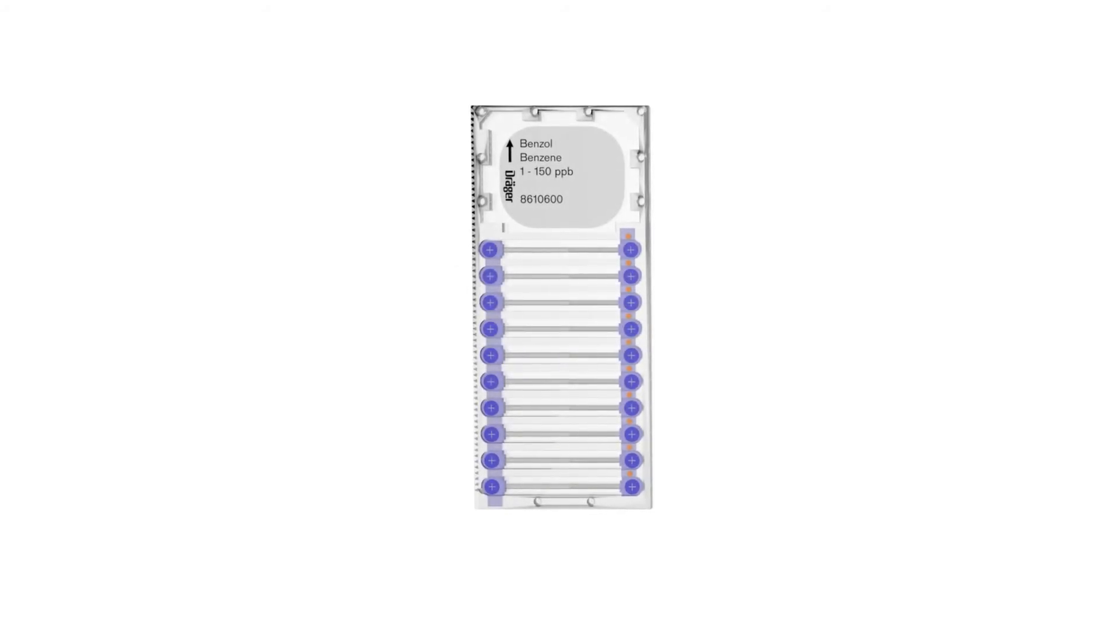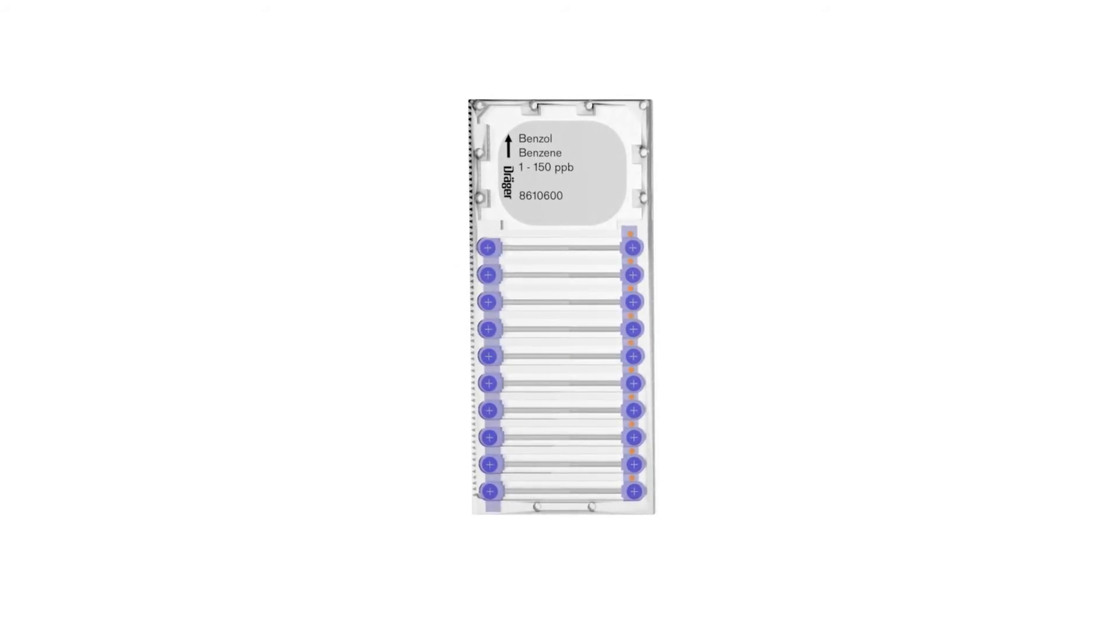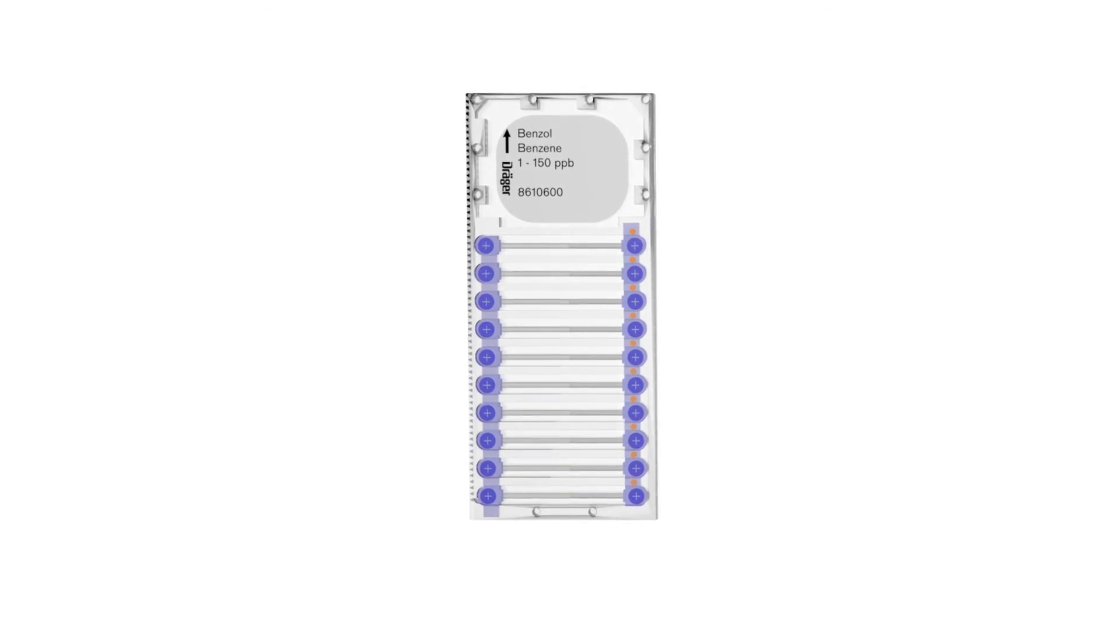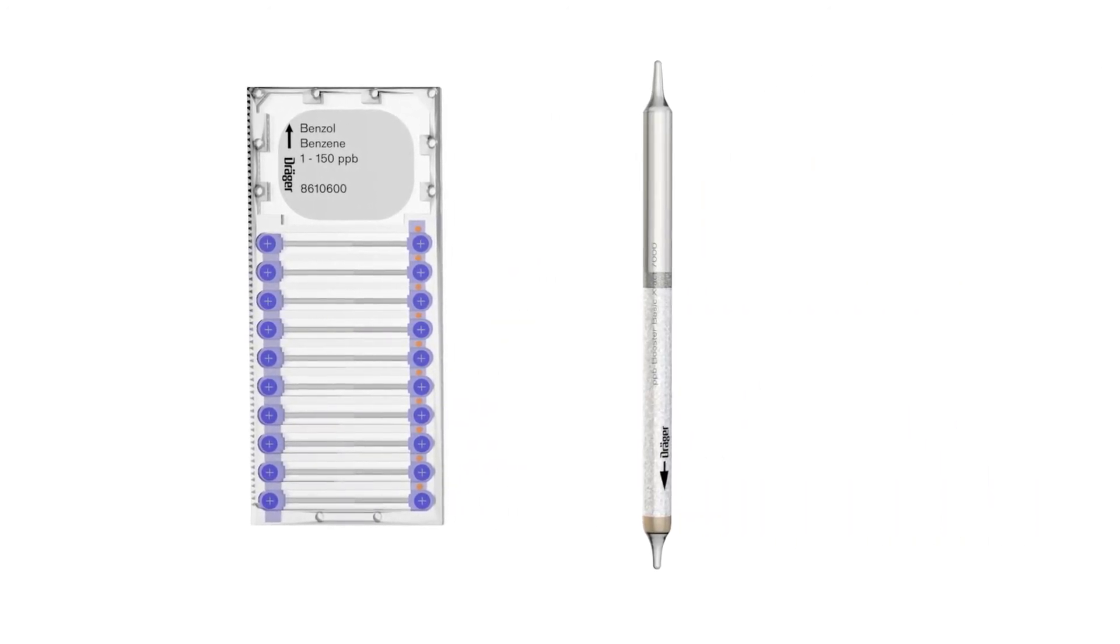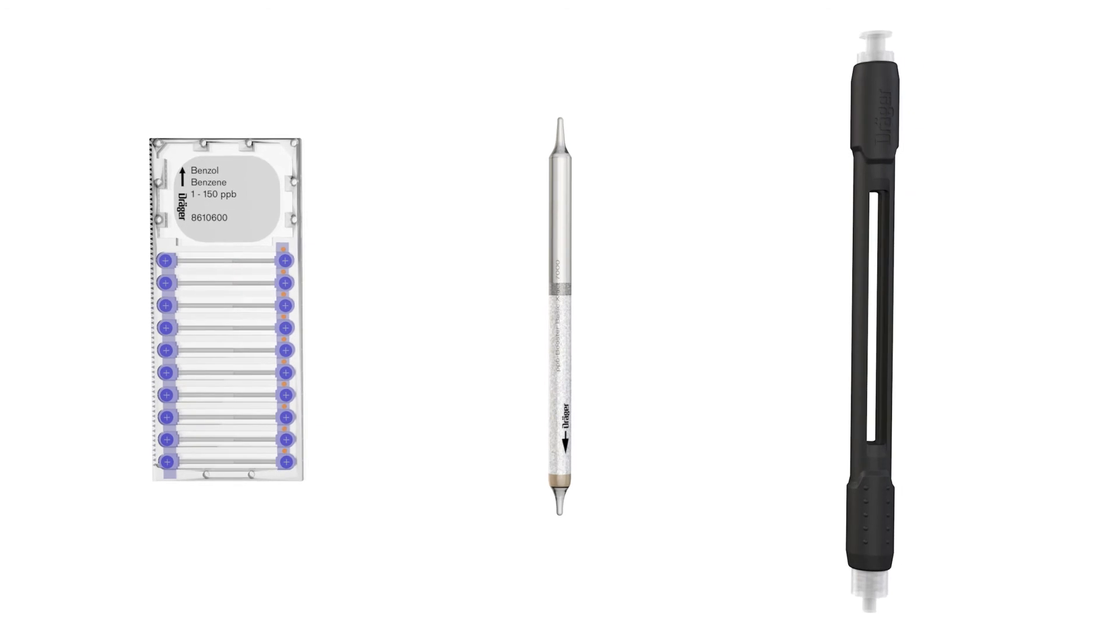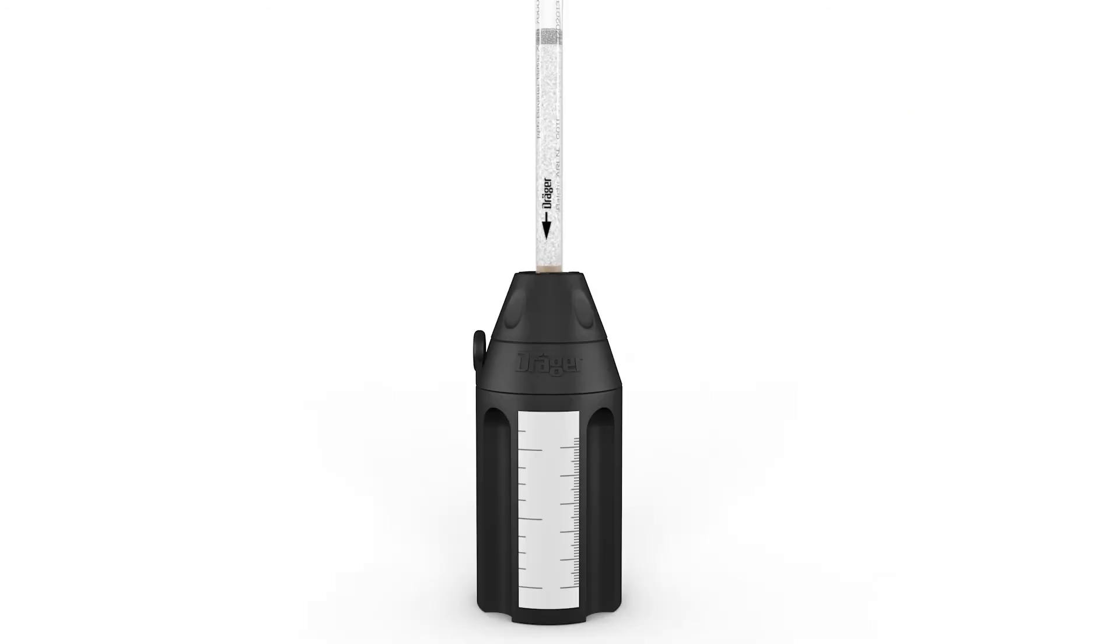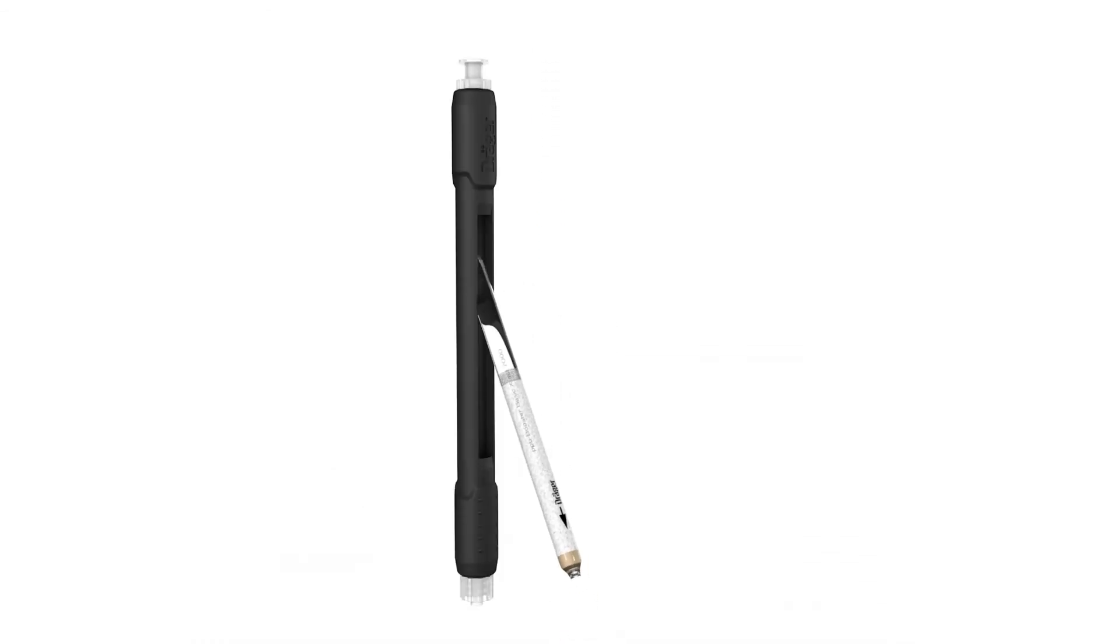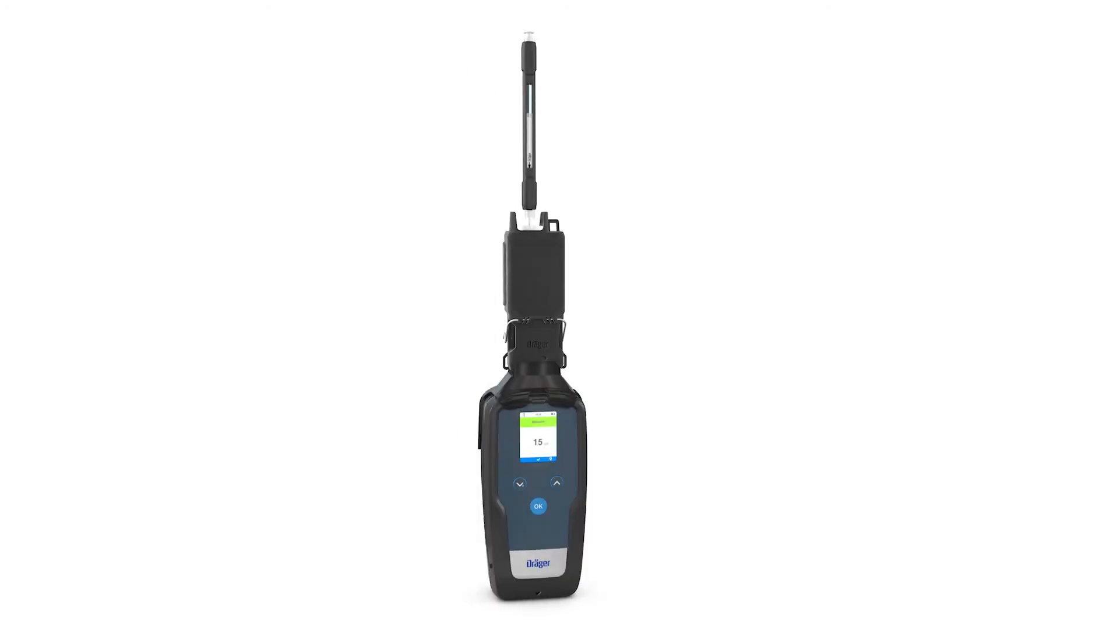To boost sensitivity and selectivity even further for some Drager microtubes, a pre-tube is required in combination with a pre-tube holder. To use the pre-tube, simply open the tip of the tube and place it into the pre-tube holder. After that, you can perform the test in the usual way.